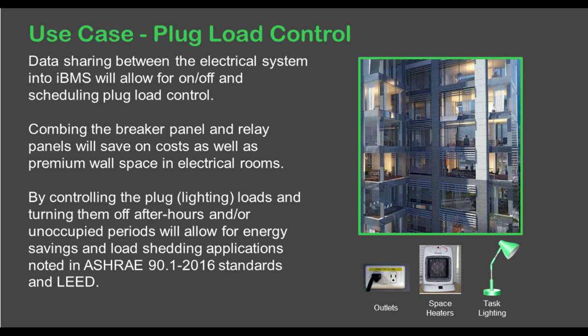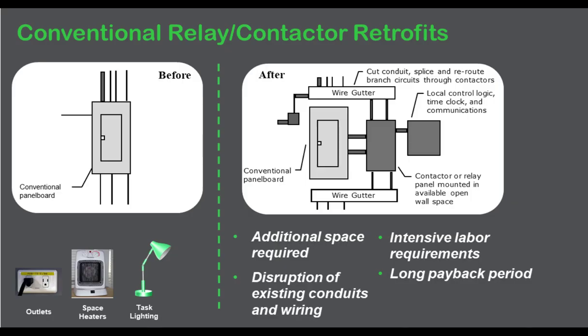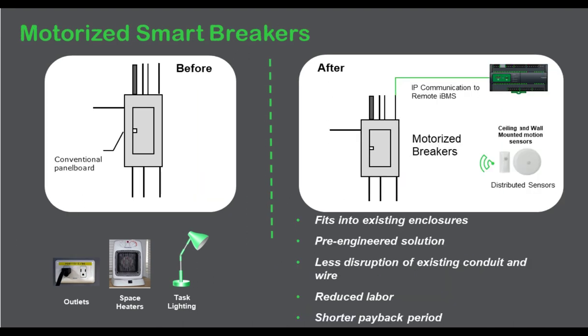Another one is plug load. We're starting to see more of this, with ASHRAE requiring it in their 90.1 2016 standard. Traditionally, you might have a standard breaker panel for lighting or lighting control, and you'd end up adding contactors secondary to the breakers plus some kind of control mechanism. If nothing else, this takes up a lot of space, and architects are really pushing for space limitations in electrical rooms, so this does affect that, especially with multiple panels.